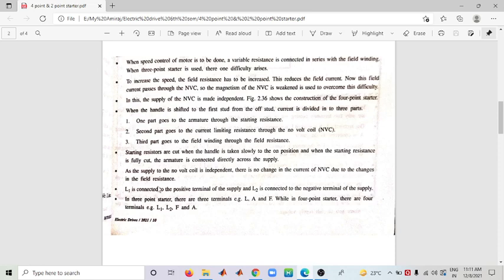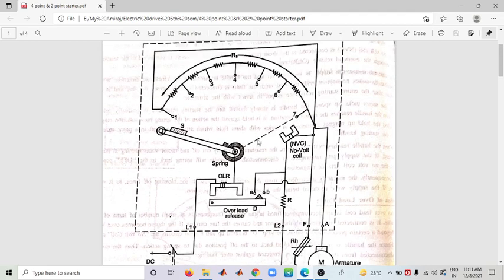Since the NVC is connected independently of the field circuit, any change in the field resistance does not affect the NVC current at all. There is no change in NVC due to changes in field resistance. This is the key advantage of the Four Point Starter — to overcome the drawback of the Three Point Starter.